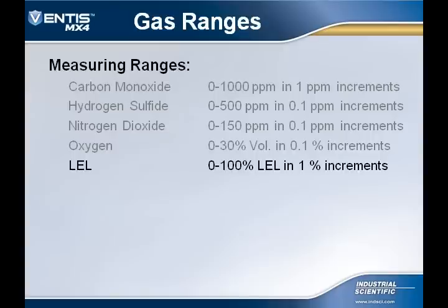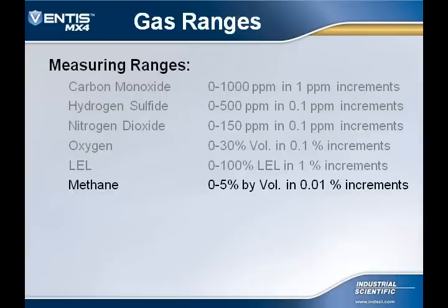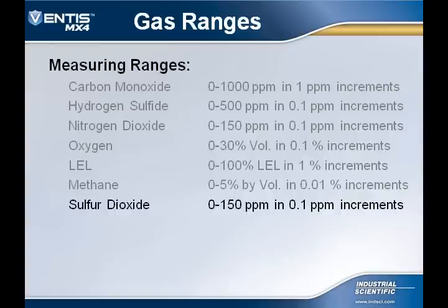The combustible sensor measuring range is from 0 to 100% LEL and measures in increments of 1%. This sensor can also be set to measure methane with a measuring range from 0 to 5% by volume and measures in 0.01% increments. And finally, the sulfur dioxide sensor. This sensor has a measuring range from 0 to 150 ppm and measures in increments of 0.1 ppm.